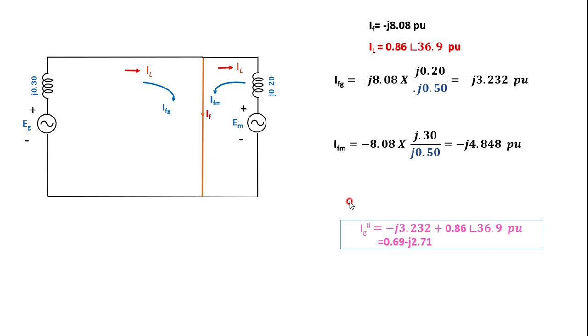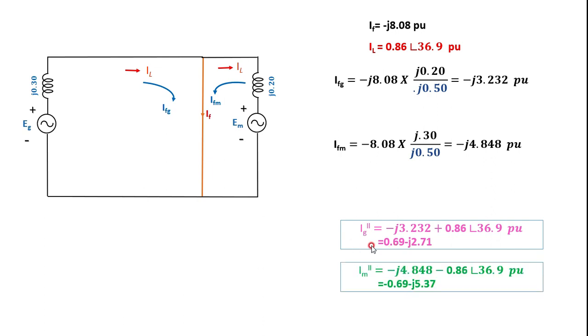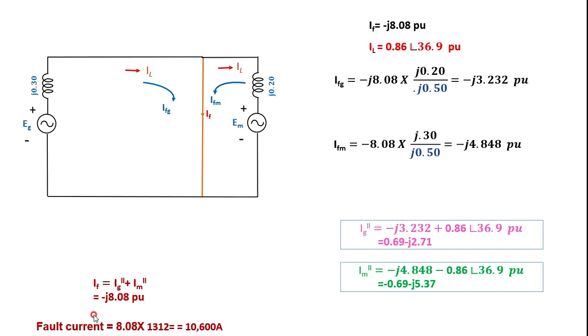Superimposing IL with IFG gives the total subtransient current from the generator IG''. For the motor, the subtransient current IM'' equals IFM minus IL, because IL flows in the opposite direction to IFM, giving -0.69 - j5.37 per unit. Verifying by adding IG'' and IM'', we again obtain -j8.08 per unit, confirming the total fault current remains 10,600 amperes.